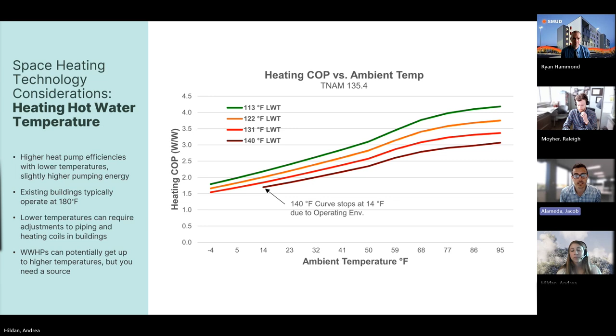So the option that is currently available for higher water temperatures is figuring out a way to use water-to-water heat pumps to get your supply water temperatures up to around 165 degrees Fahrenheit. That's kind of what's shown here. If you have a good water source to pull from, you don't have to do what you see on the screen here. You can just generate 165 degrees Fahrenheit from whatever your water source is.